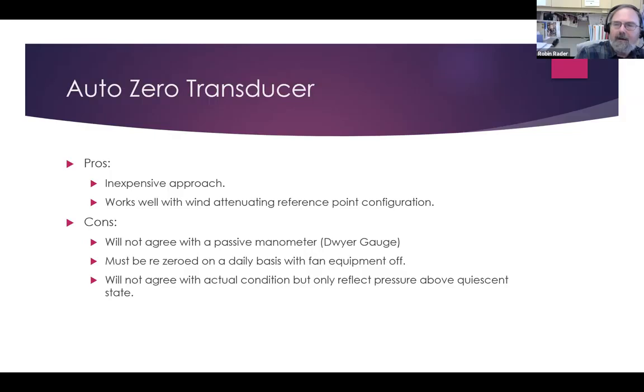I personally like to have a standard gauge next to the transducer that is reading the same thing that the transducer is reading. Whereas with auto zero, this would not happen because the transducer is being set with a new 0 point every day, and the Dwyer gauge would not be.